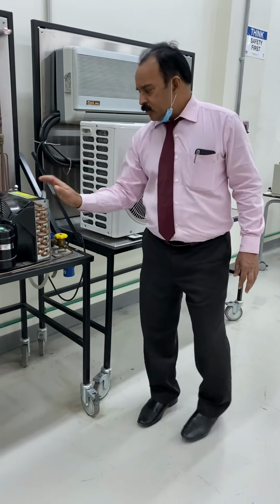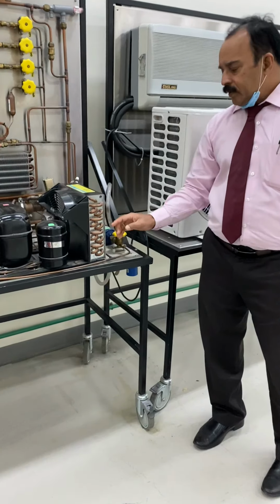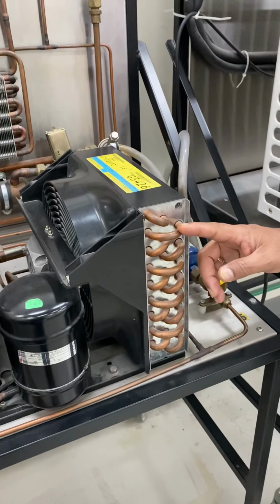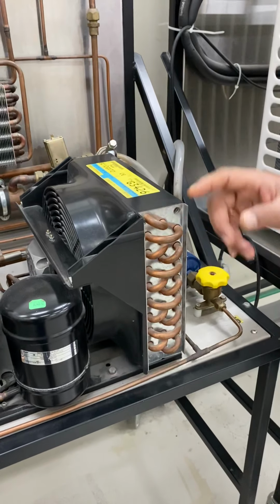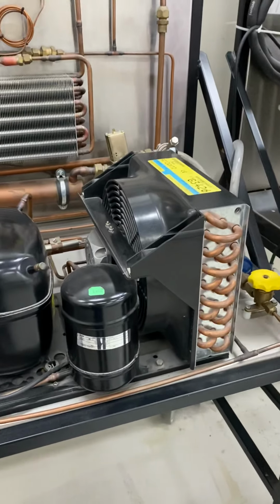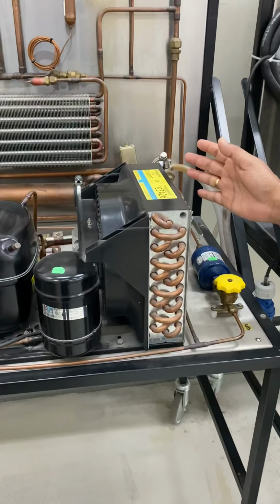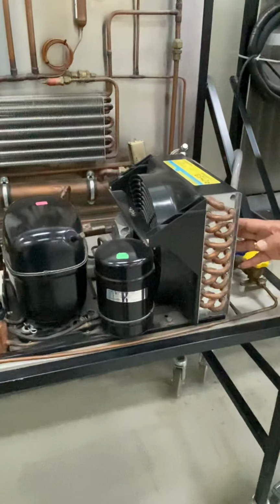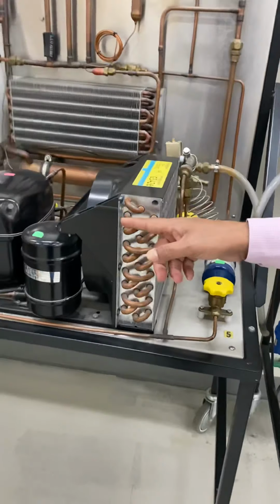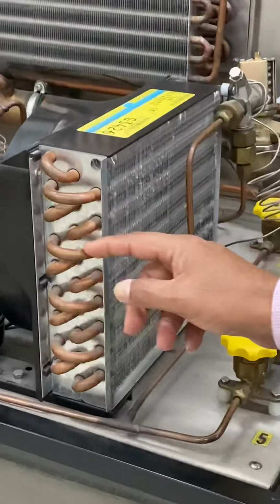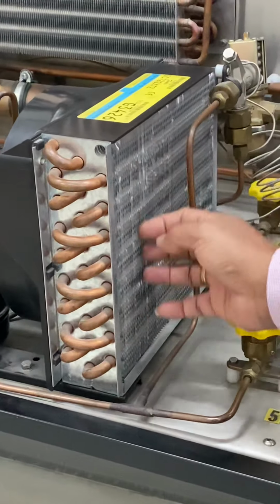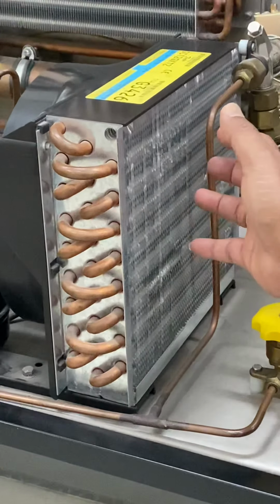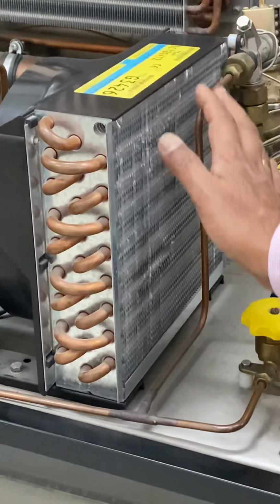Here this is one condenser, and you can see the coil here. Inside the condenser there will always be high pressure refrigerant gas coming from the compressor. This will be condensed and then it goes to the dryer and then the expansion valve. You can see the cooling is taking place. The copper tubes are here, these capillary tubes, and also the fins. These fins increase the heat transfer area for proper cooling. That is why this is one typical type of condenser.